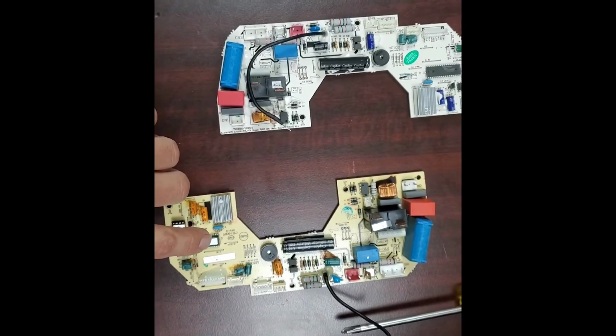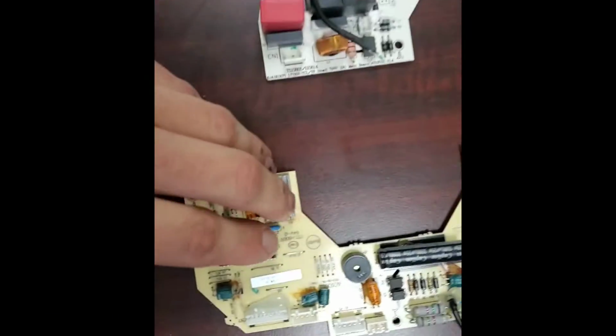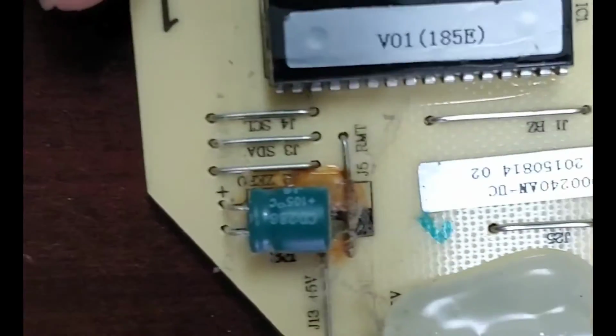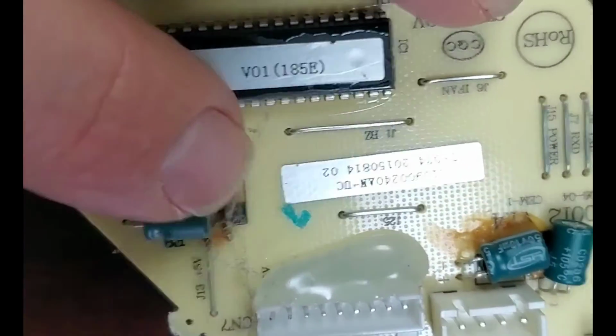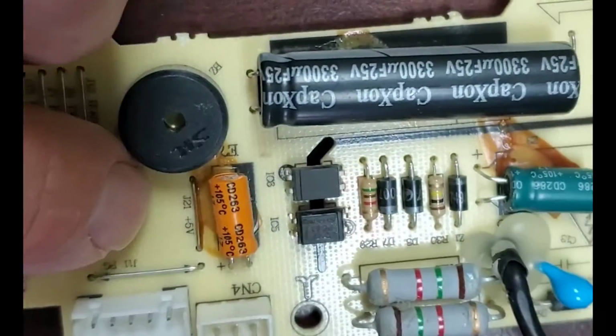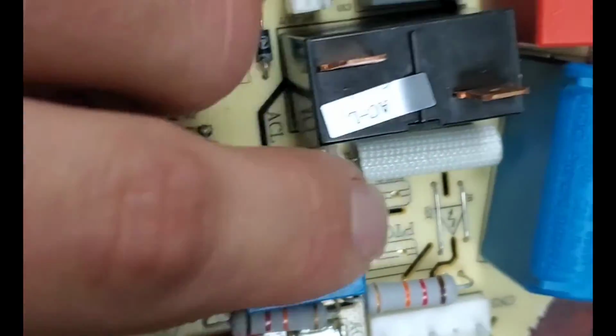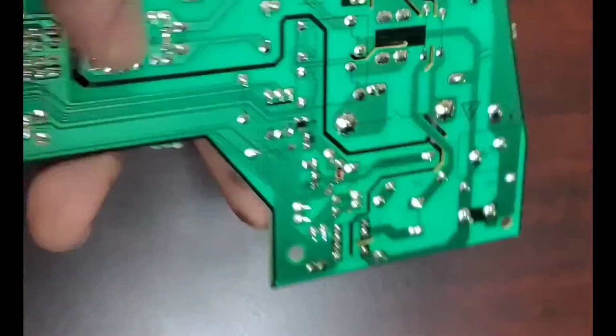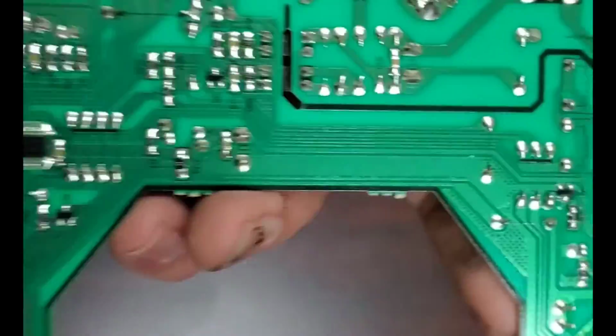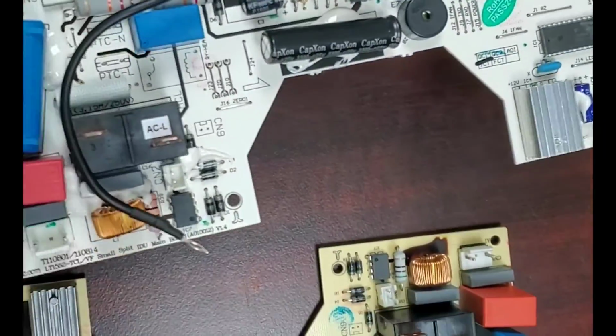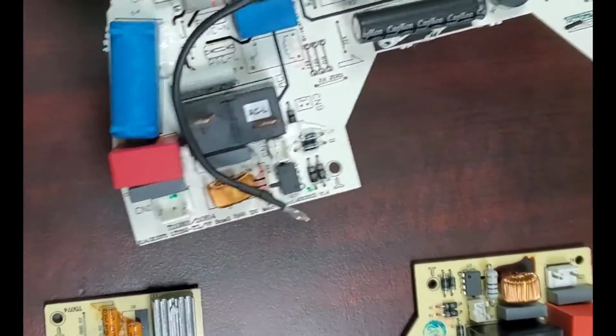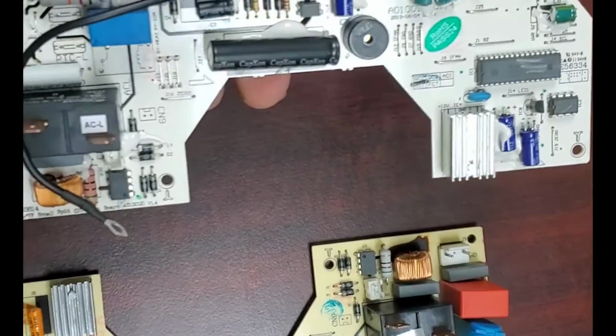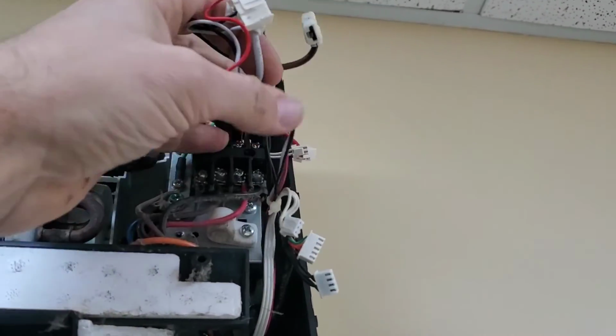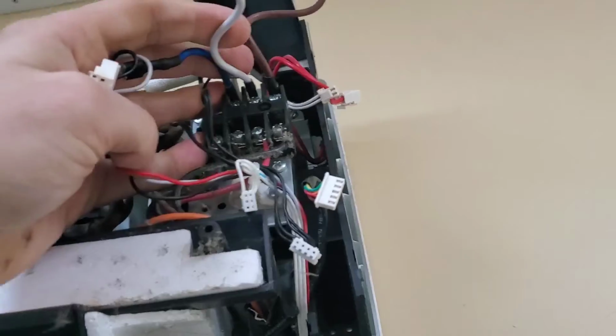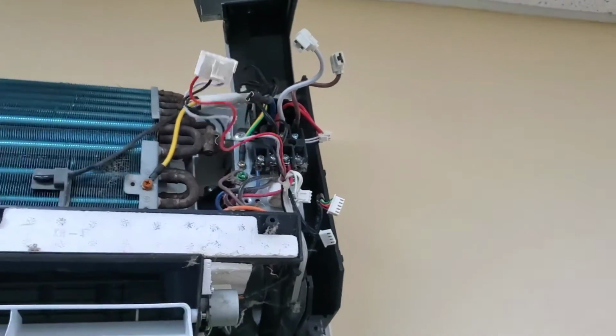So, an old board and a new board right next to each other, and as you can see, I've pulled the old board out, and this is what you find. This corrosion, these burnt brown looking spots on this actual board. So this board is definitely the problem. If you have an E6 in the field and your fan motor will run, it most likely could be your board. All these plugs are going to go on the new board. We're going to put the new board in and turn the unit back on and see if the code clears.